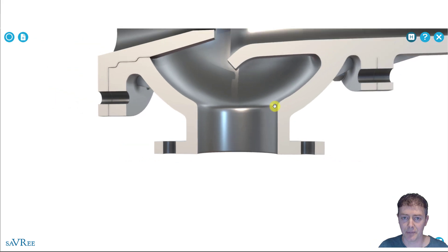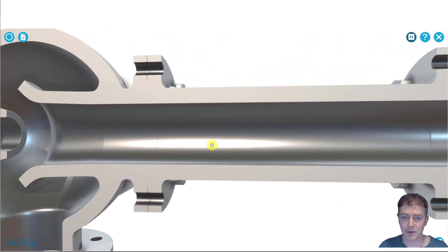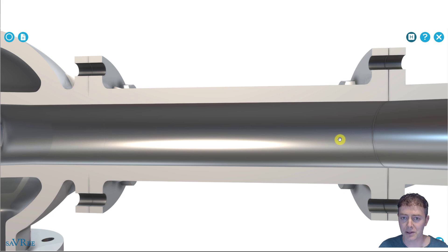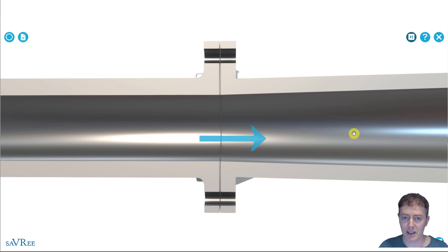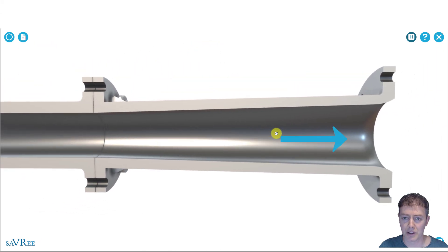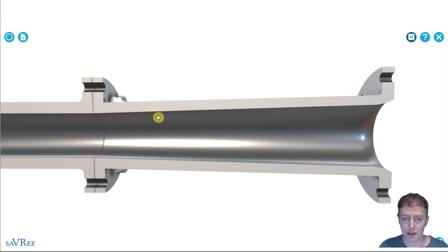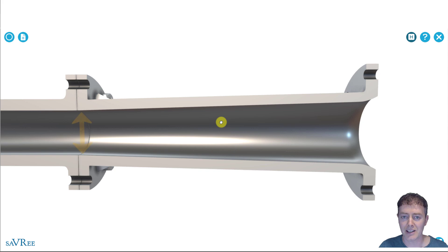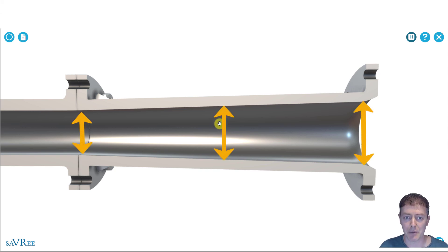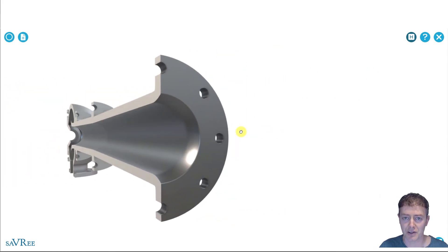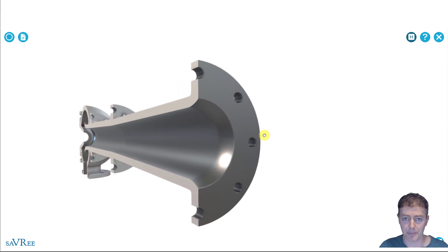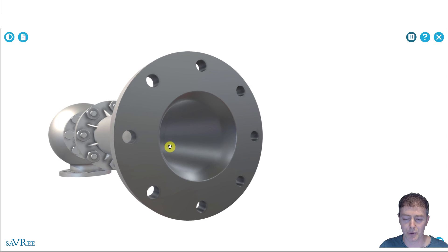As our motive fluid flows into the converging inlet nozzle, we're going to get a suction pressure that draws in our suction fluid, also known as our secondary fluid. Those two fluids will then flow along through a section called the throat or mixing throat. They will then begin to pass through what's called a diffuser or diffuser nozzle, also called a diverging nozzle, which gets gradually wider — its internal diameter gradually increases as we progress from the suction side to the discharge side. At that point, our fluids have been mixed and we discharge them through the discharge flange.